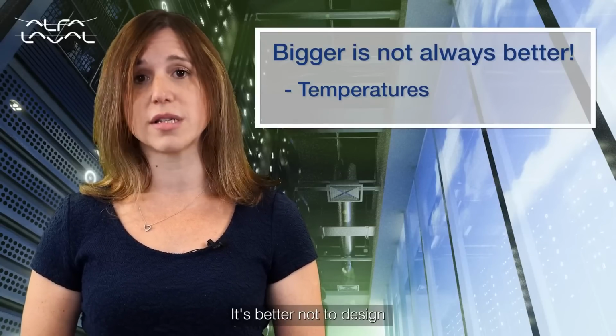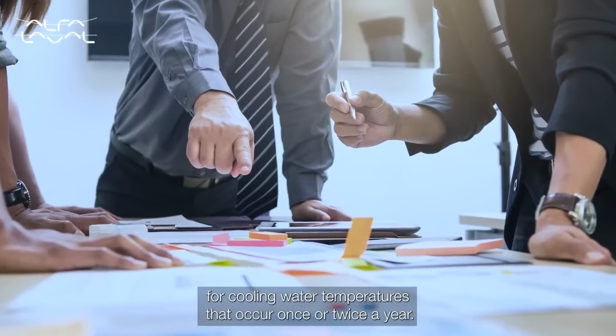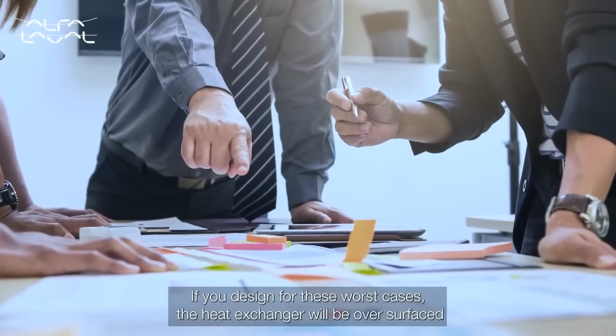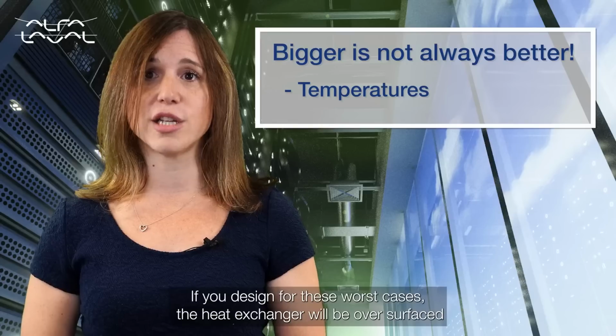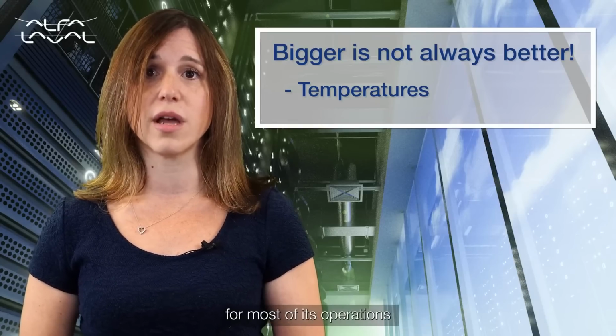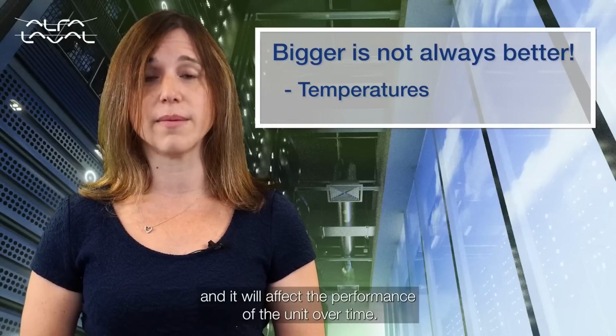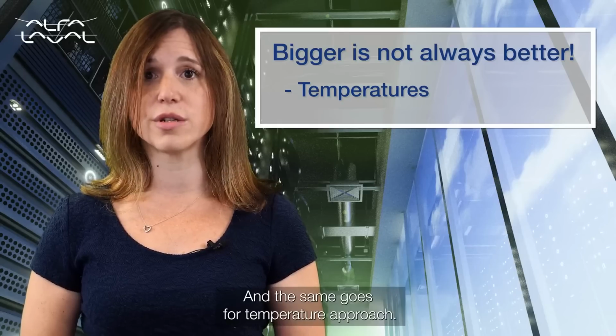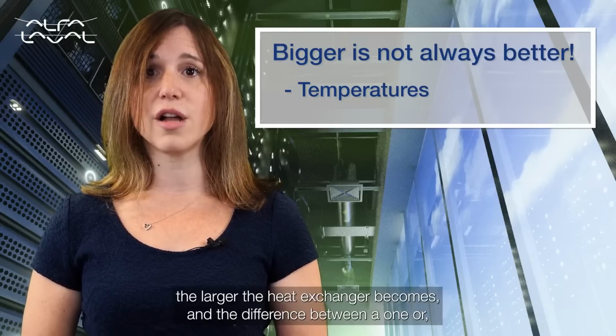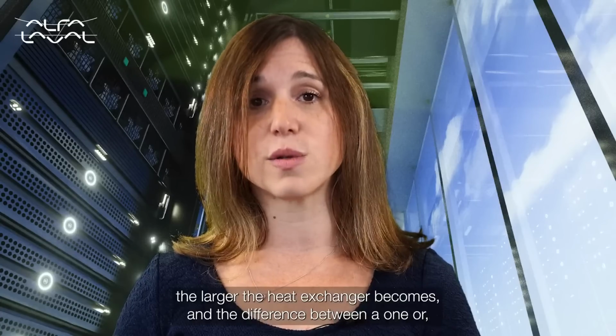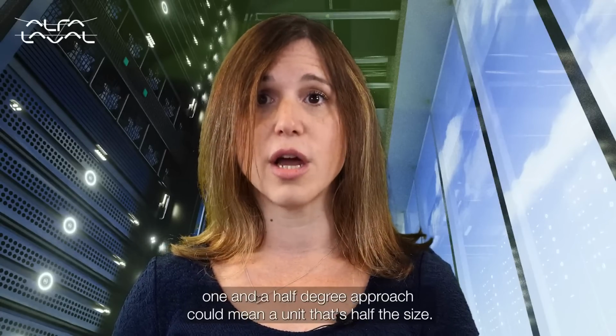It's better not to design for cooling water temperatures that occur once or twice a year. If you design for these worst cases, the heat exchanger will be over surface for most of its operation, and it'll affect the performance of the unit over time. And the same goes for temperature approach. The closer the temperatures are, the larger the heat exchanger becomes, and the difference between a 1 or 1.5 degree approach could mean a unit that's half the size.